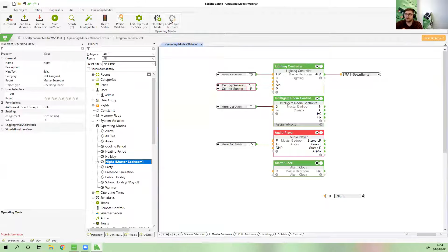But this is great for all of the other rooms in the house, not so great for the master bedroom, because actually, in fact, we probably don't want the lights in the master bedroom to turn on at all when it's night mode. We want the motion sensor, the presence sensor, to be disabled during nighttime. And that is very easily done. On the lighting controller, we have an input DISP, which prevents the motion sensor or presence sensor from bringing on lights. So then what do we connect to DISP? Simple. We've already got it. We've got the night operating mode. I already showed you if you drag it out as an input. So just have that connected to DISP.